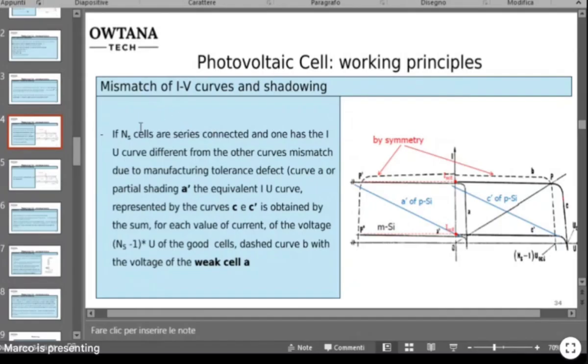If a certain number of cells, n, are connected, and one has an IV curve different from the others due to mismatch from manufacturing tolerance defects (curve A) or partial shading (A prime), the equivalent IV curve, represented by curves C and C prime, is obtained by summing, for each value of current, the voltage of n minus 1 good cells (dashed curve B) with the voltage of the weak cell A.